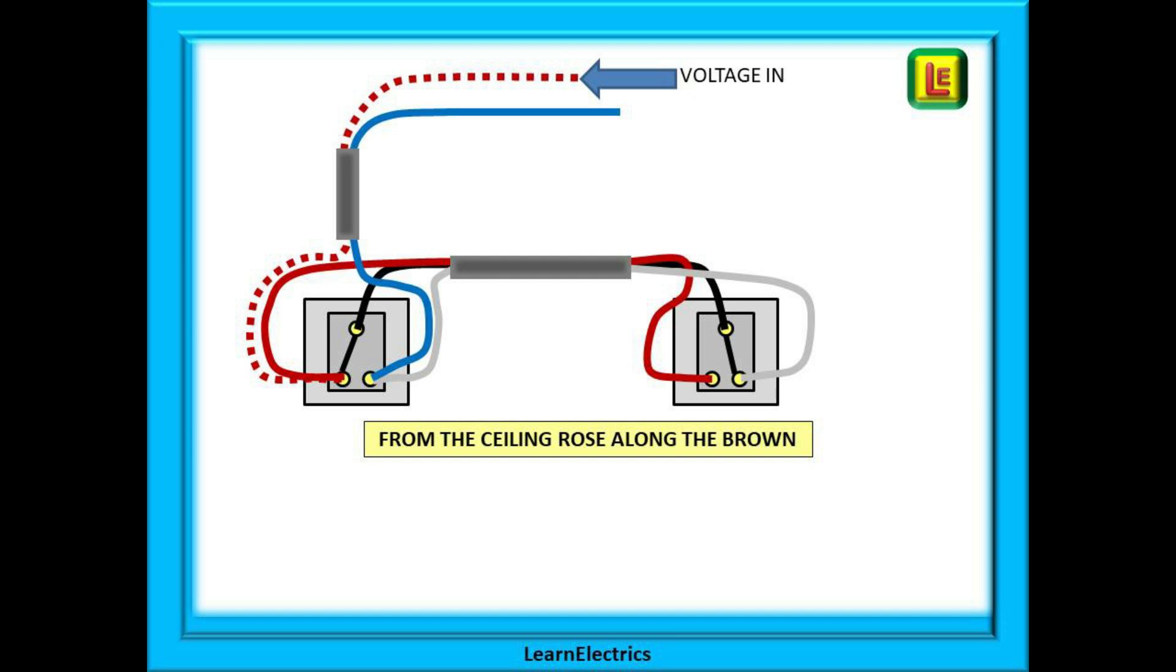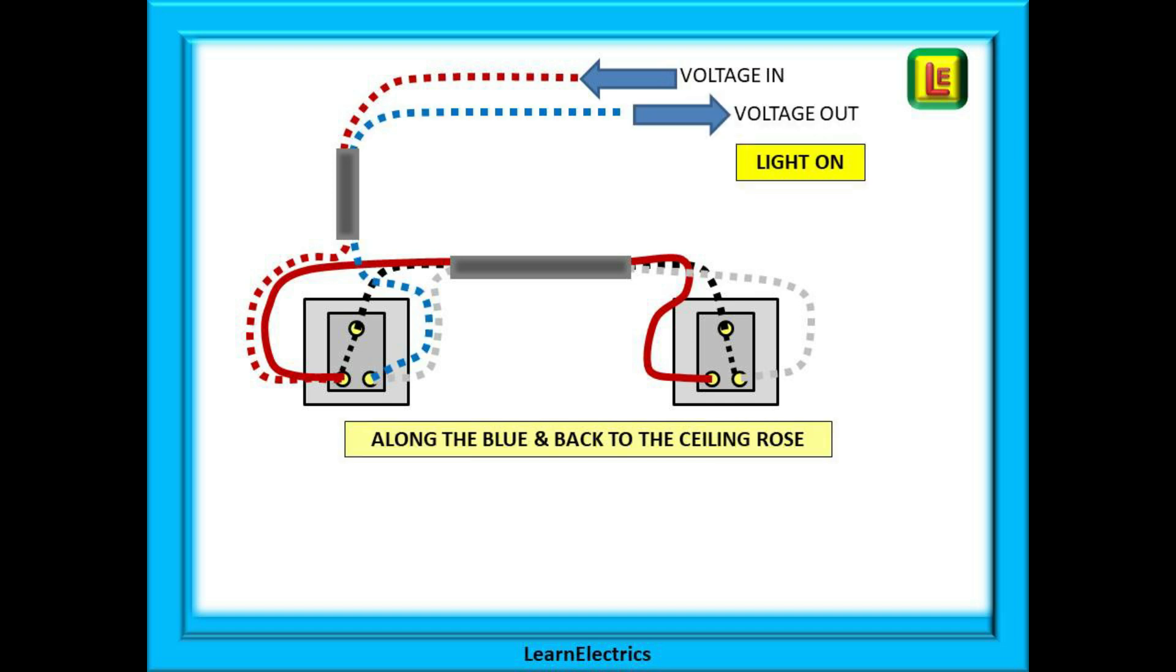The voltage travels along the switch wire to L1 of the first switch, and now through the switch to the common terminal, along the black strapper wire to the common terminal of the second switch, and then to the L2 terminal. From L2 along the grey strapper wire to L2 of the first switch, along the blue wire back up the switch wire to the ceiling rose where it causes the light to come on. And the circuit is in fact complete.